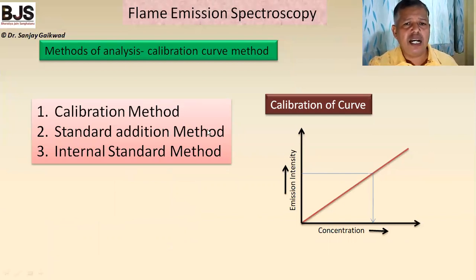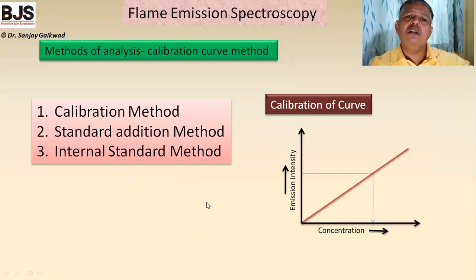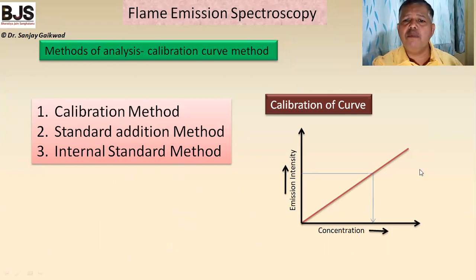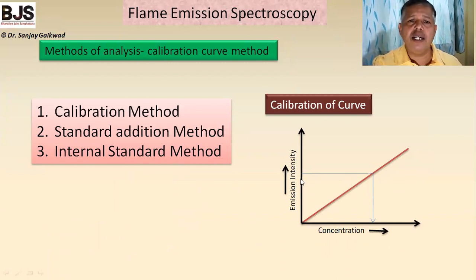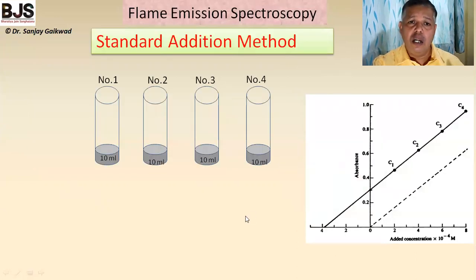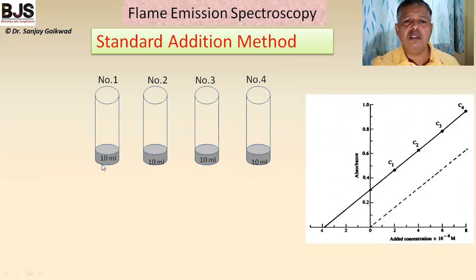For the calibration method, five standard solutions are taken and a standard graph is plotted by measuring the emission for each concentration. Then the unknown solution is aspirated and its emission intensity is measured. From that intensity and the standard graph, the unknown concentration can be found.